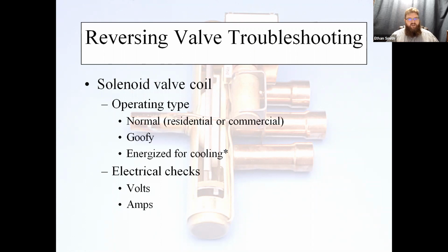So you've got to know what valve you're looking at. Electrical checks on a valve, whether it's getting power or not. If it's getting power, typically on the back of the valve there's a little metal screw. You should be able to magnetize to that with a little steel screwdriver. Amperage into that valve body as well. You can check to see if it's energized or not without having to pull the tabs off. It's usually less than an amp on those little solenoids.